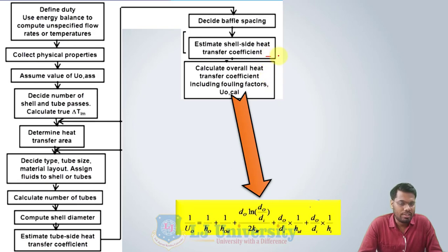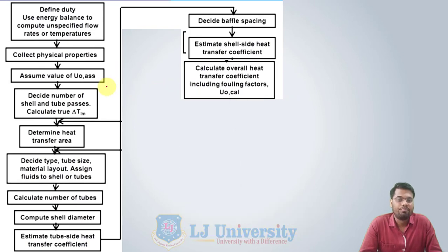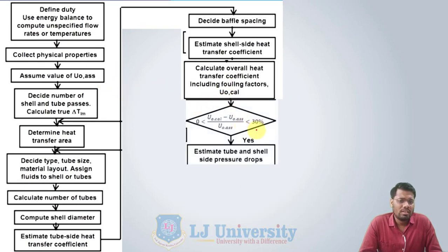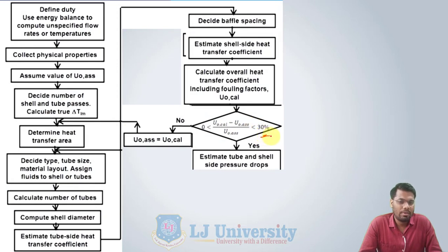After getting the shell side heat transfer coefficient, we can easily calculate the overall heat transfer coefficient including the fouling factor, using the equation discussed in the first chapter. We then compare this calculated overall heat transfer coefficient with the assumed overall heat transfer coefficient. If the value is within 30 percent, we can proceed further. If not within the allowable 30 percent, we have to change the assumed overall heat transfer coefficient based on the calculated value and repeat all the steps again.